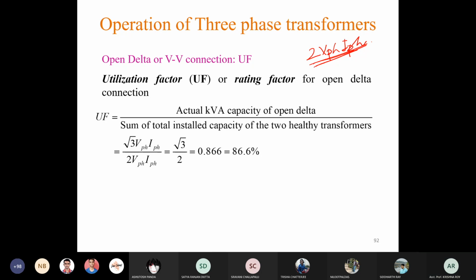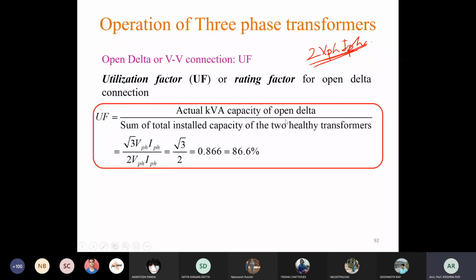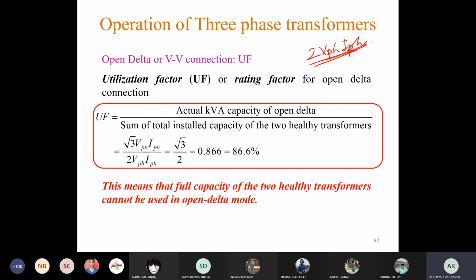Is it clear? Yes, sir. Only you are responding. Yes, sir, we're getting it. Fine. So that is the utilization factor. This means that the full capacity of the two healthy transformers cannot be used in open delta mode. So this is one disadvantage of open delta connection. Only 86.6% of total available capacity can be utilized.